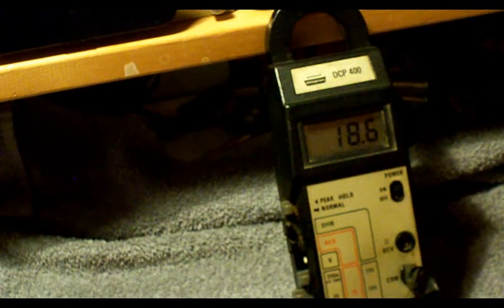Yeah, I had that on the 10 volt range. Yeah, I'm just checking the meter here. So that's set correctly now. So we have 18 volts. So that's with no load on the transformer. 18 volts. Okay? So this transformer is good. So we'll disconnect it. Okay, so this transformer is good. So now we're going to go ahead and hook up the defective transformer.